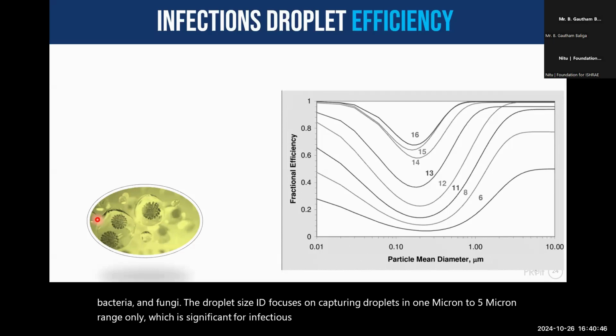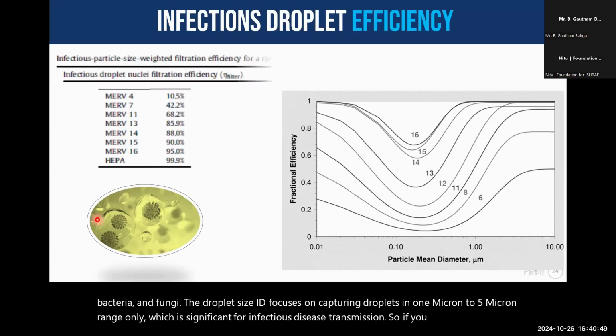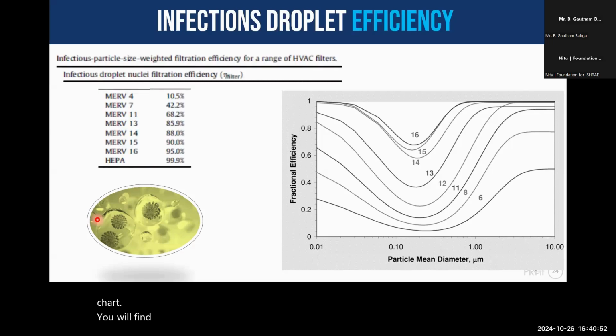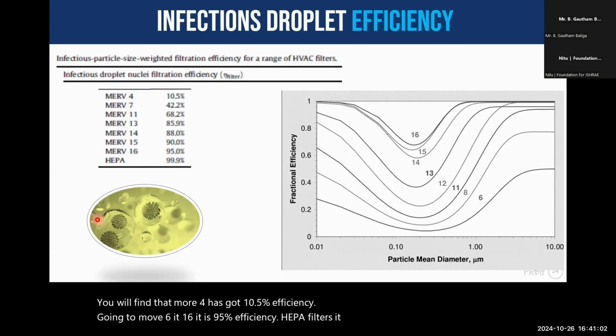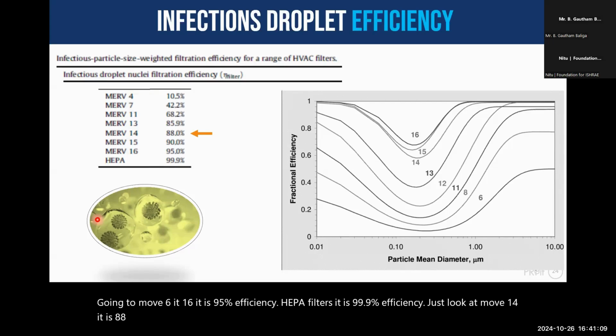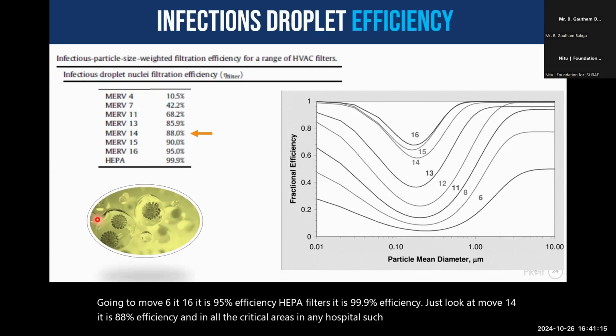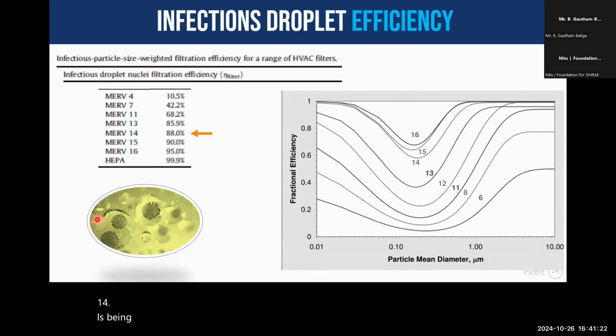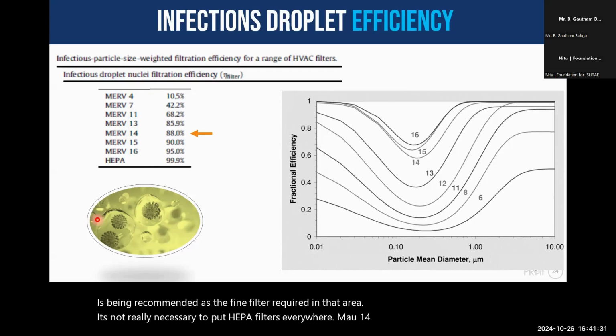infectious disease transmission. So, if you see this particular chart, you'll find that MERV4 has got 10.5% efficiency. Going to MERV16, it is 95% efficiency. HEPA filters, it is 99.9% efficiency. Just look at MERV14, it is 88% efficiency. And in all the critical areas in any hospital, such as in ICUs, you'll find that MERV14 is being recommended as the fine filter required in that area. It's not really necessary to put HEPA filters everywhere. MERV14 can do a good job.